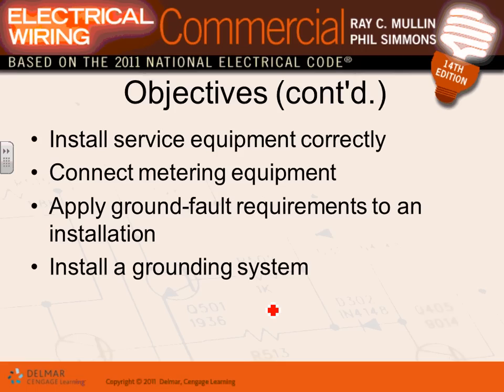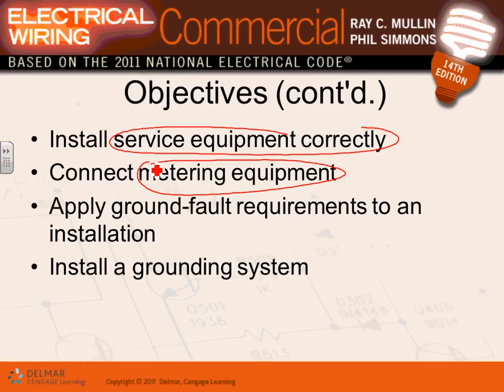Installing service equipment correctly and connecting the metering compartment for the service equipment. For the project, Brian, that we had, you guys put the CT cabinet outdoors and you put the meter next to the CT cabinet, right? That's one way of doing it. You're going to see it now. There are a couple of other ways of doing it.